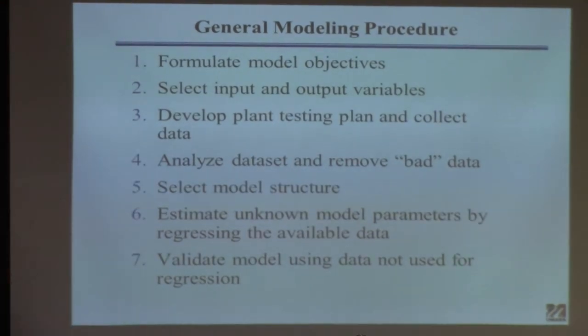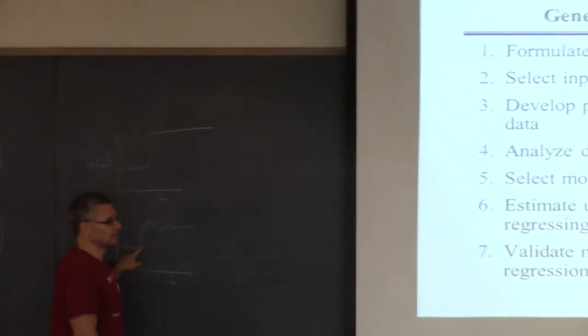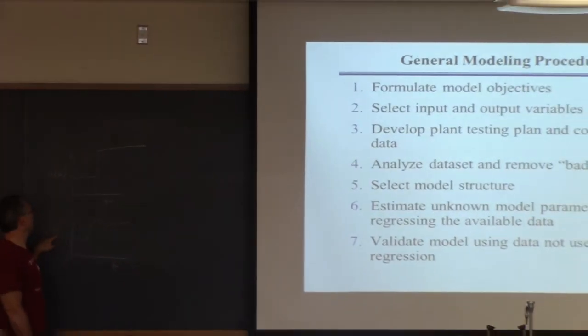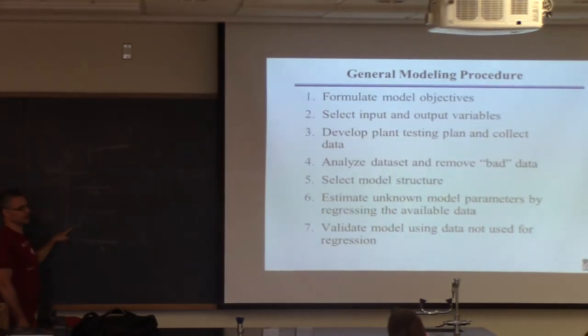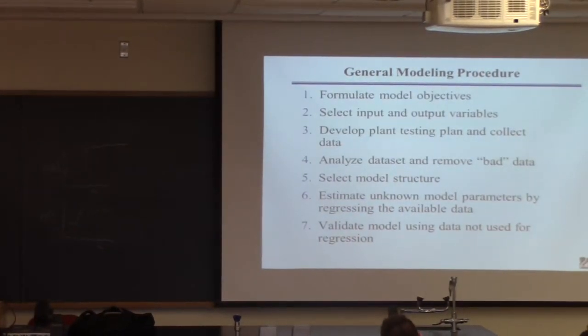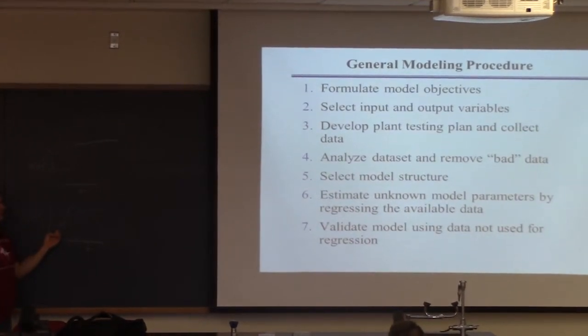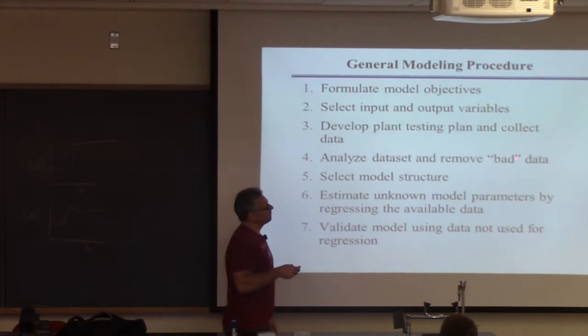So you analyze the data, which means you look at this data and see if it makes sense. Like, should this go up if this goes up? Sometimes the output will go in the opposite direction than you think. Then you go to the operations people and say, what were you doing last Tuesday at three o'clock? And they're like, we were changing a valve on the distillation, the reflux valve. You're like, okay, throw the data set away. My experience is a quarter to a third of the data is bad. Just isn't good. You just have to dispose of it.